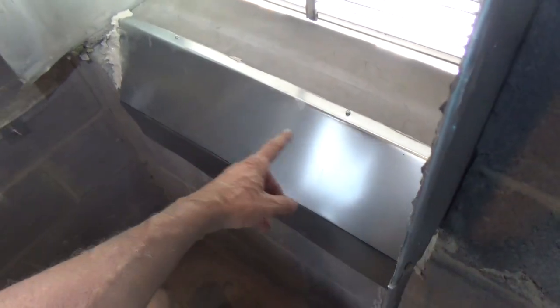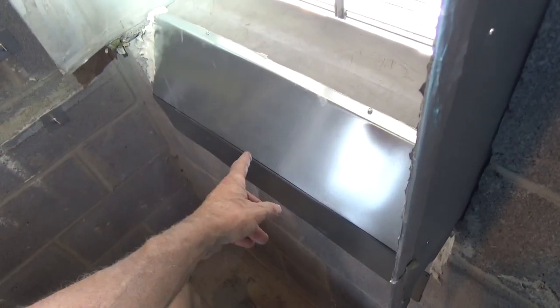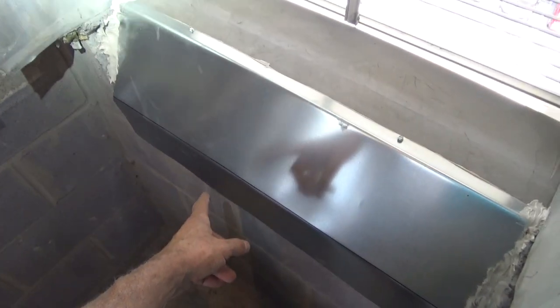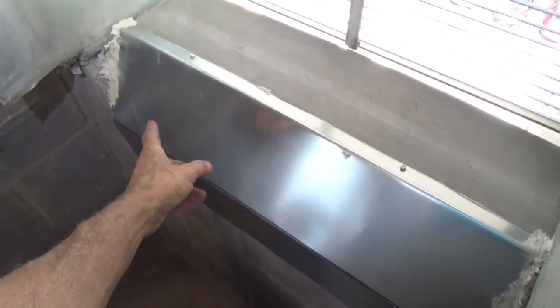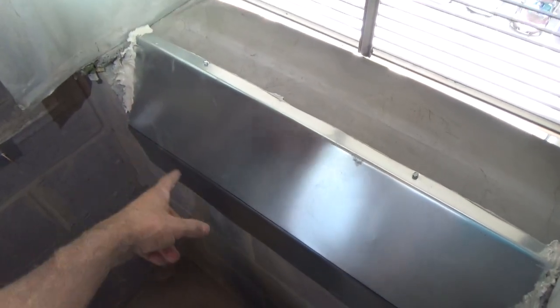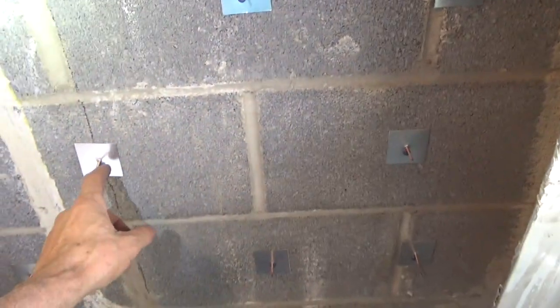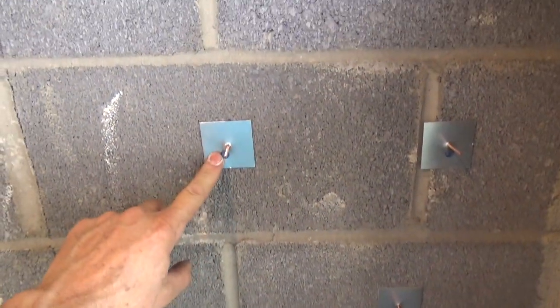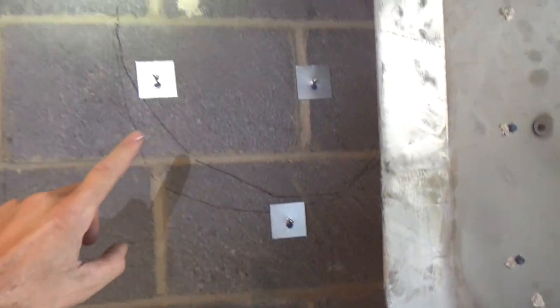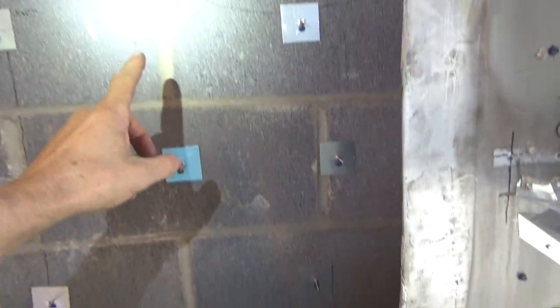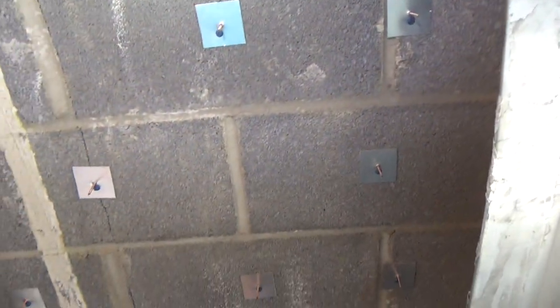Now this is just for the 2.5 ton. It's like 1.5 hours to knock that brick out. 2-ton you don't need it because you're only going down 6-inch. We went down 8-inch, so I went ahead and just made better airflow. So right now I'm putting pins and I'm securing them with Tapcons, and this will hold the insulation along with silicone on the wall too.